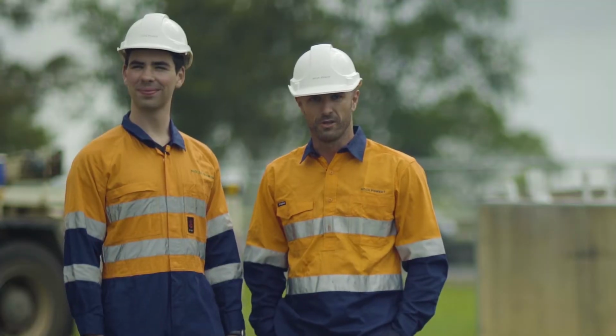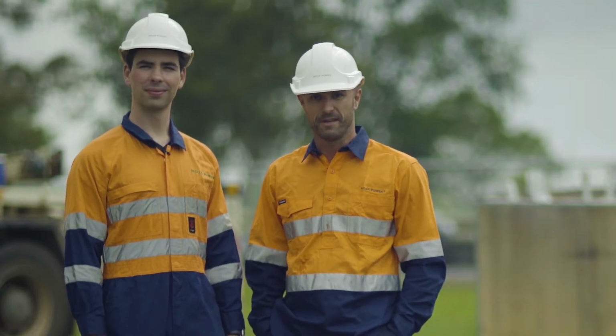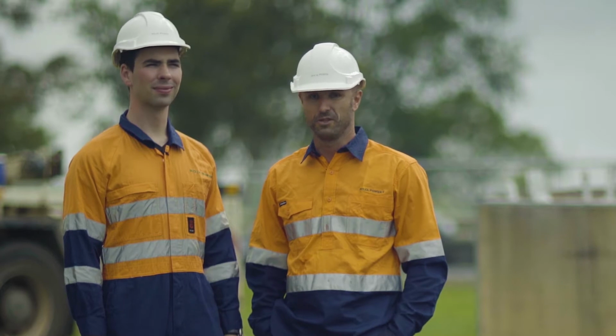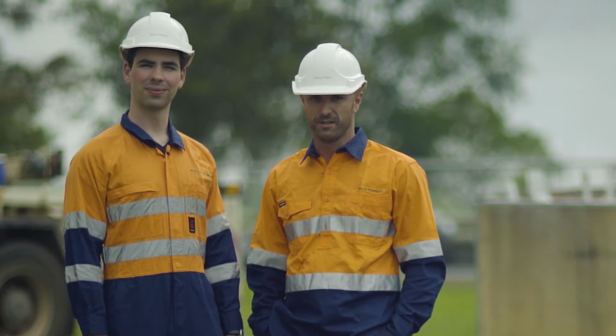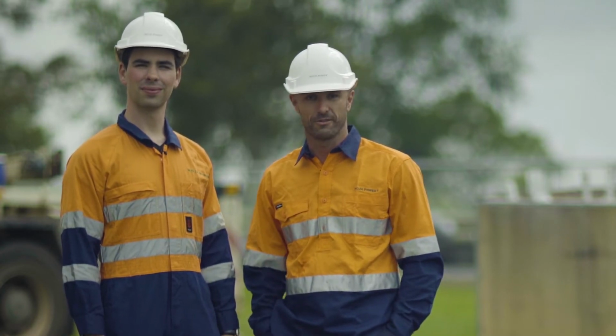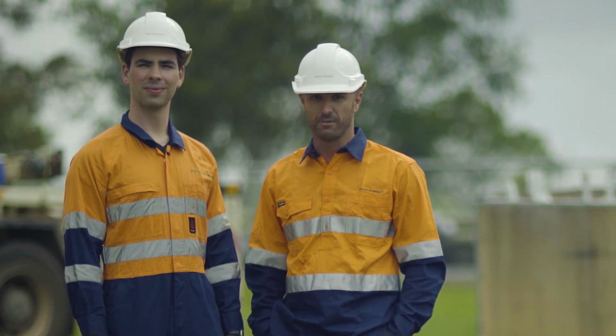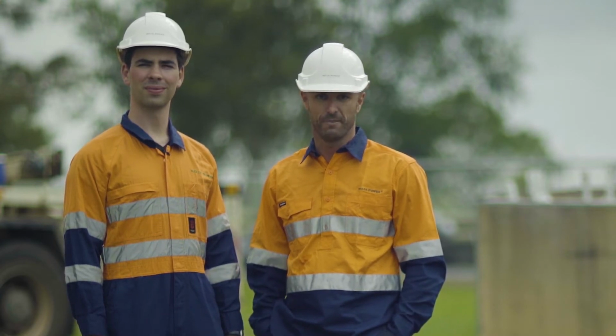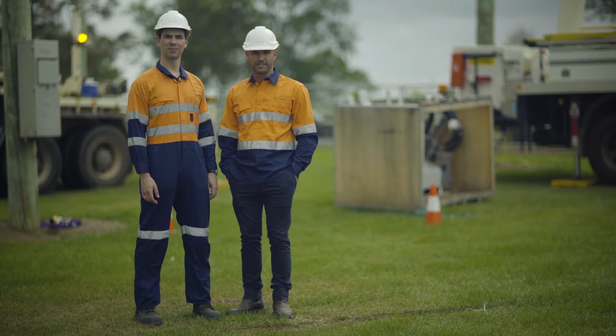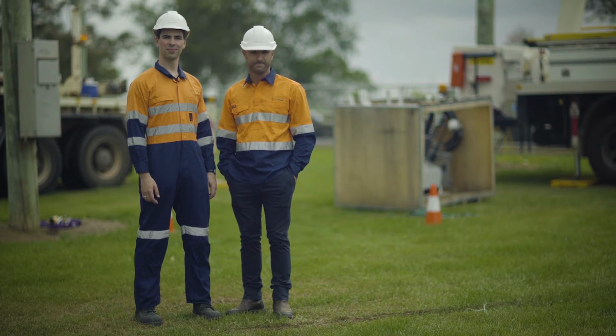Now, before we install a NOJA Power recloser, it is recommended that we check the installation section of the user manual and familiarise ourselves with the procedures. There's also a great installation video available on YouTube. Just search NOJA Power. For best installation safety practices, it's recommended that what work can be conducted on the ground is completed prior to lifting the recloser in the air.